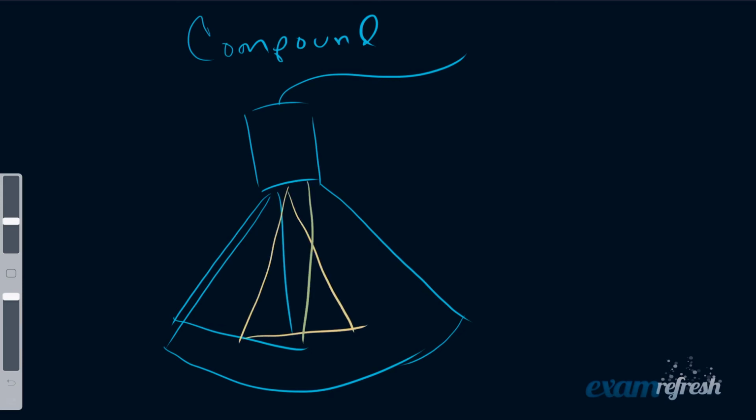Well, if we have a structure that's sitting back there, and the machine receives an echo from both the first angle of insonation and the second angle of insonation, it can assume that something belongs there. So it'll actually place that dot. But if it only receives it from one angle and not the other one, then it's assuming that's noise. So this will reduce the speckle.